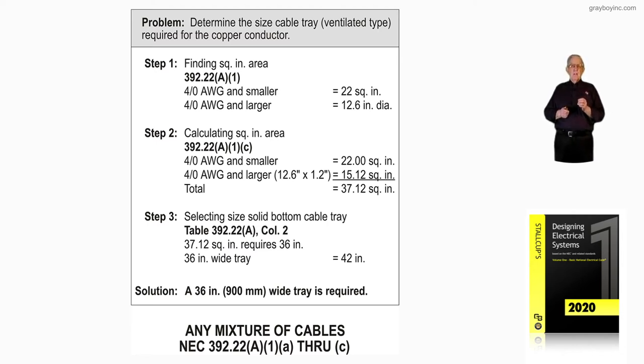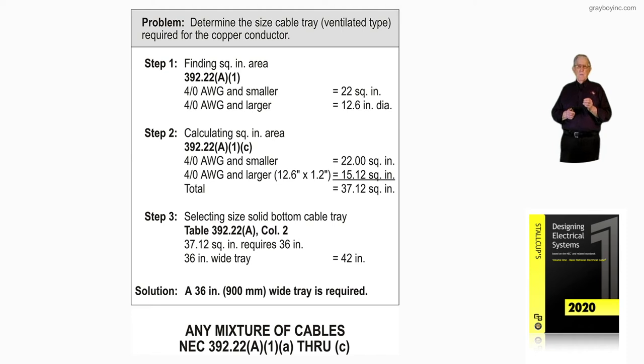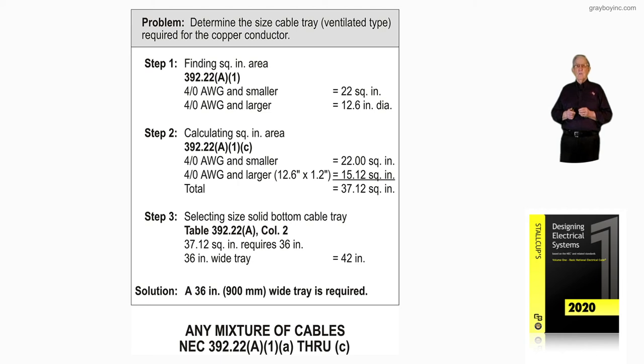Step two is the application of 392.22A1C. The 4/0 and smaller was listed as 22 square inches, but the 4/0 and larger cables was 12.6 inch diameter. The table in that column said take 1.2 times 12.6, and we come up with 15.12 as a square inch area. Total it: 37.12 square inches, putting everything into square inches.